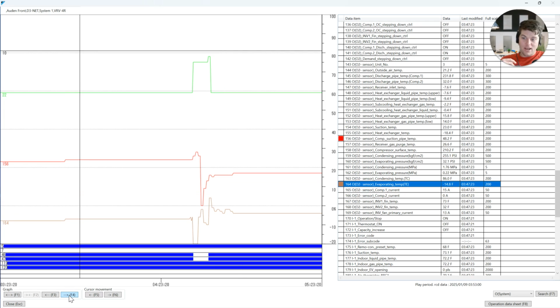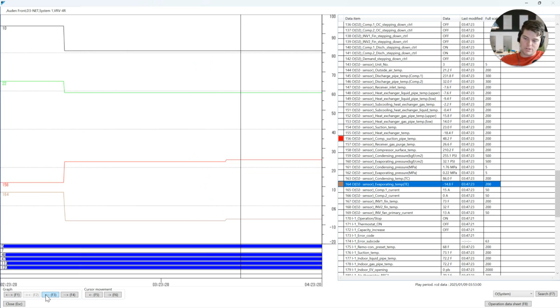It's not good. And whoa, here we go. That's what I like to see. It breaks the 50 mark. Now we're close to getting into the 60s of suction superheat. It's not good. That's the answer. Suction superheat, it's in the toilet, right? Discharge superheat, it's in the toilet. It's not good. Both of those are awful, which tells me I'm not getting enough vapor back to my compressor.